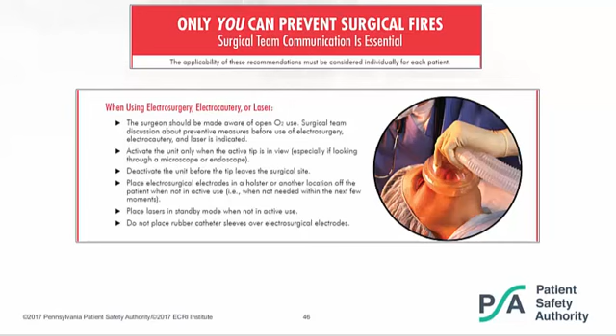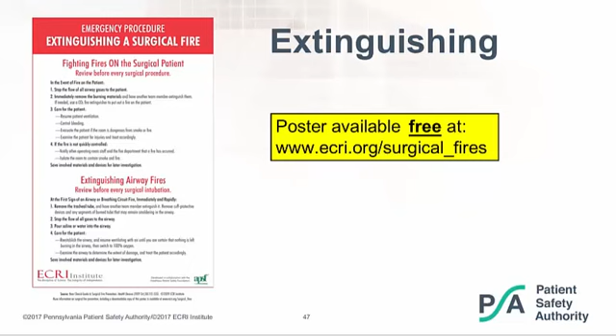Lasers should be put in standby mode when not active, and please do not put red rubber catheters over an electrosurgical electrode to make them better insulated. If you do that, you are modifying a medical device, and that red rubber catheter is not a very effective electrical insulator at the extremely high voltages that come out of a Bovie tip. Plus, it's very flammable, especially in an oxygen-enriched atmosphere. So if you want better insulated electrosurgical electrodes, buy them.